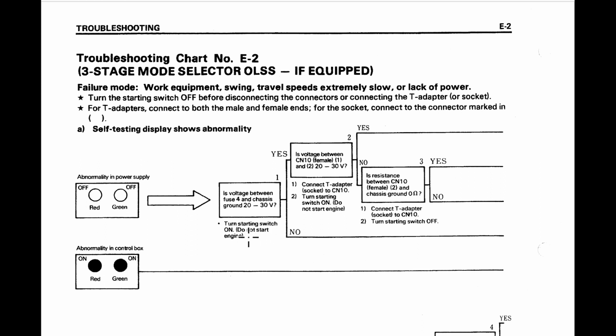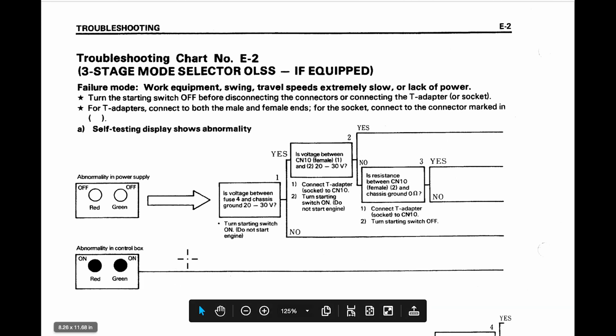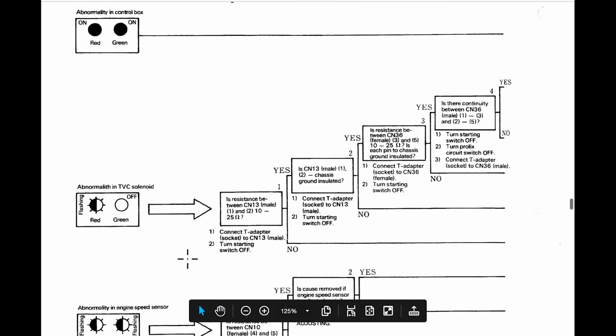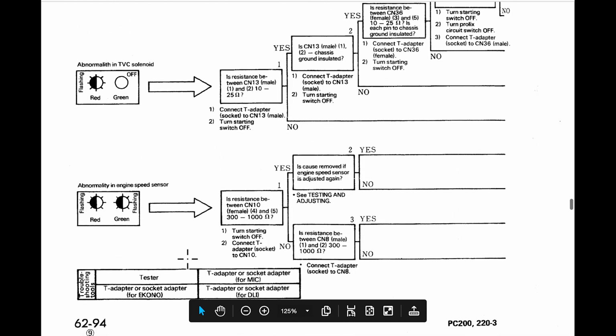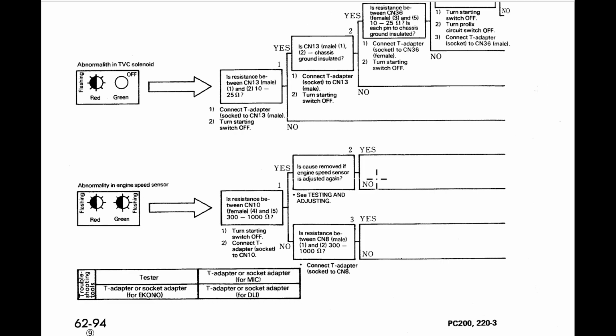And it'll give you a condition to put the machine in. In this case, it's a voltage between CN10, between 1 and 2, 20 to 30 volts. So you'll answer the question. If it's no, you go down and ask another question. If it's yes, it'll come up here and you follow the line out. For each configuration listed here that could be on that computer, it runs you through these flow charts.